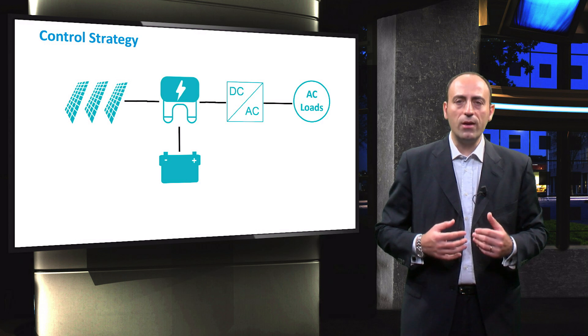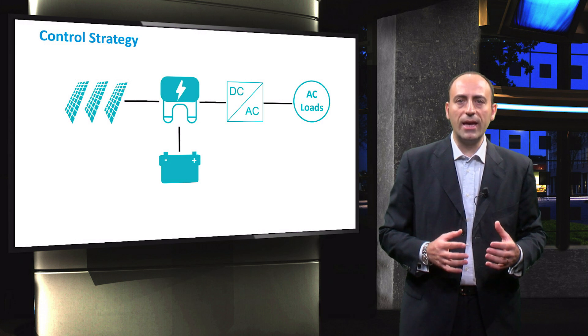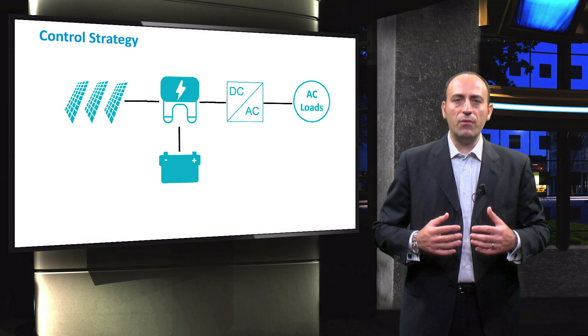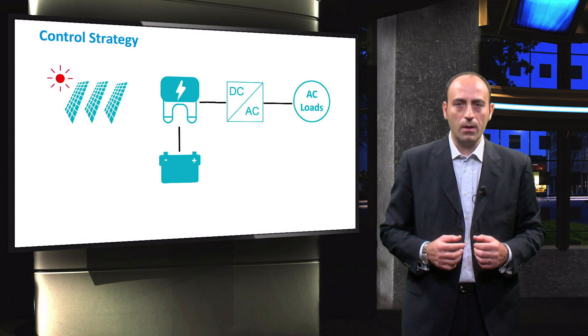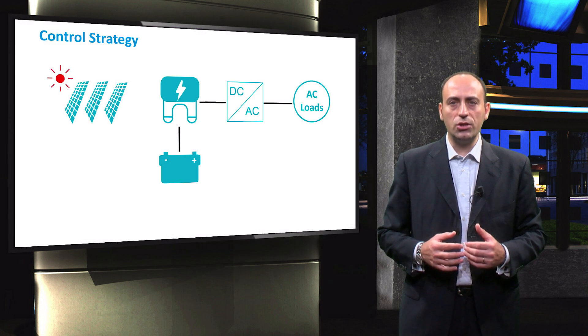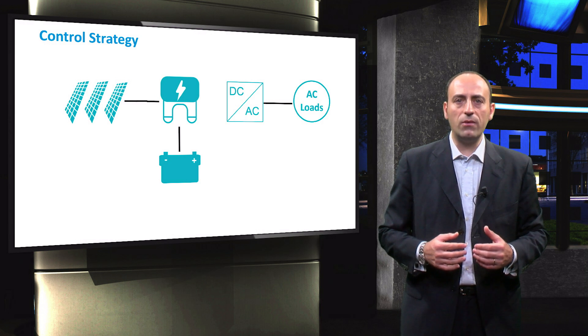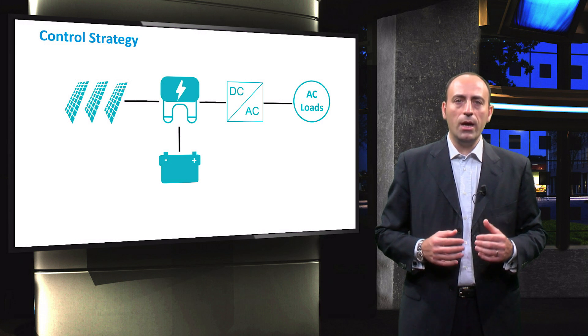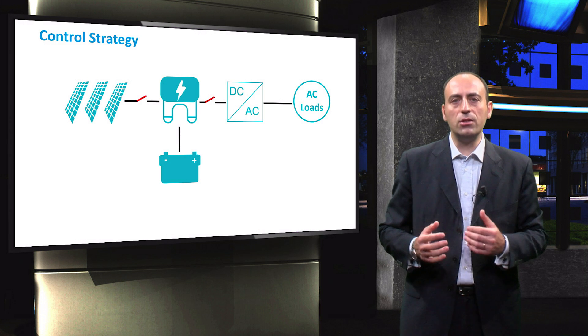The charge controller not only regulates the flow of current in the PV system, but also prevents the batteries from getting overcharged or over-discharged. The charge controller prevents overcharging of the battery bank by disconnecting them from the PV array. Similarly, they prevent over-discharging of the battery bank by disconnecting the loads from the battery bank after the batteries reach a certain level below the state of charge value. In the control strategy algorithm, a switching mechanism is set up to mimic such functions, typically operated by the charge controller itself.